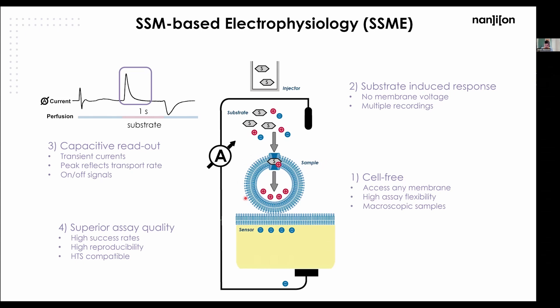Here in this picture you see vesicles adsorbed to the sensor — actually it's millions of them — which enables high signal amplification compared to patch clamp. The second point is that we are measuring substrate-induced responses. Our devices are essentially pipetting robots that inject substrates to the sensor, and that substrate gradient stimulates the transport activity. This happens at zero millivolt — there is no voltage clamp — and you can measure multiple recordings sequentially because in between recordings the substrate is washed off and initial conditions are restored.